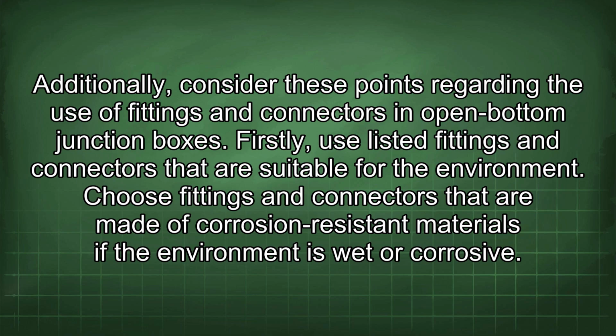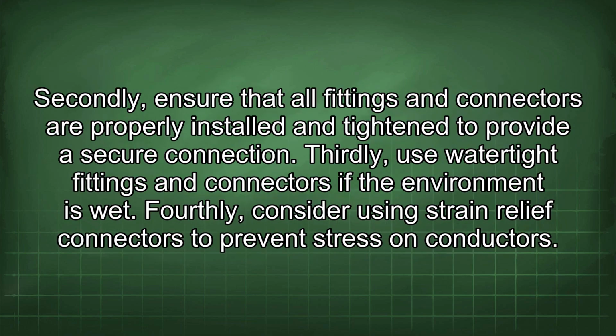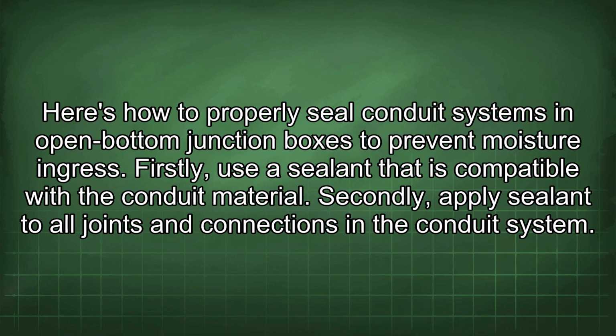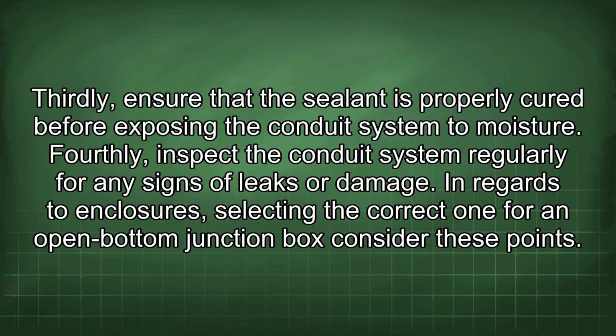Additionally, consider these points regarding the use of fittings and connectors in open-bottom junction boxes. Firstly, use listed fittings and connectors that are suitable for the environment. Choose fittings and connectors made of corrosion-resistant materials if the environment is wet or corrosive. Secondly, ensure that all fittings and connectors are properly installed and tightened to provide a secure connection. Thirdly, use watertight fittings and connectors if the environment is wet. Fourthly, consider using strain relief connectors to prevent stress on conductors. Here's how to properly seal conduit systems in open-bottom junction boxes to prevent moisture ingress. Firstly, use a sealant that is compatible with the conduit material. Secondly, apply sealant to all joints and connections in the conduit system. Thirdly, ensure that the sealant is properly cured before exposing the conduit system to moisture. Fourthly, inspect the conduit system regularly for any signs of leaks or damage.